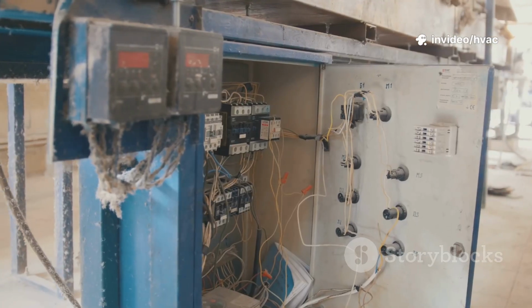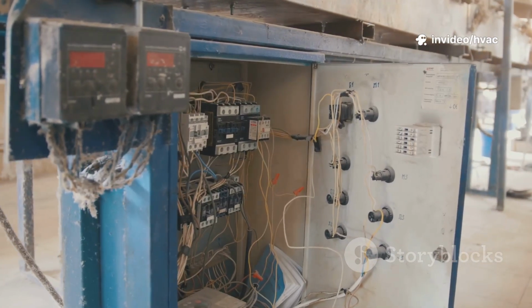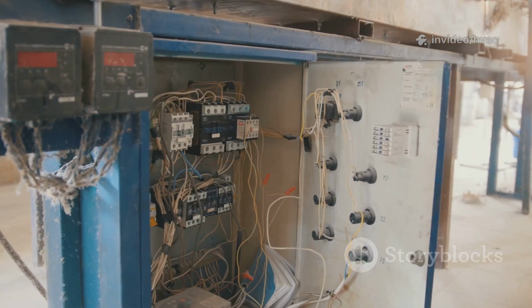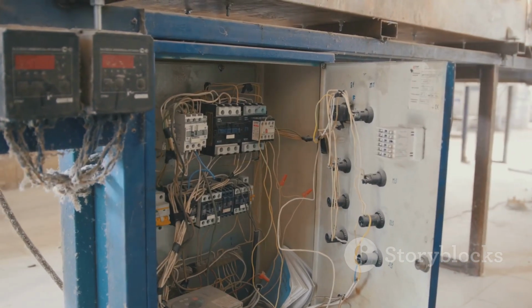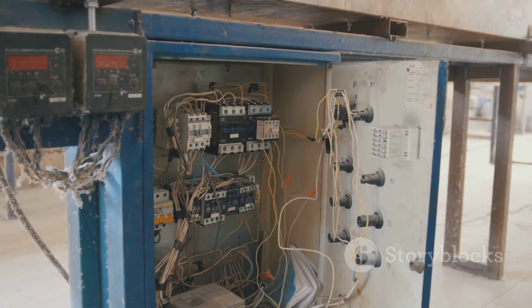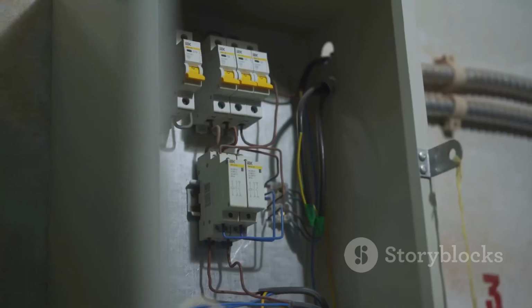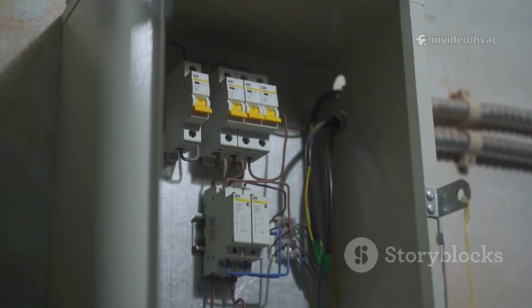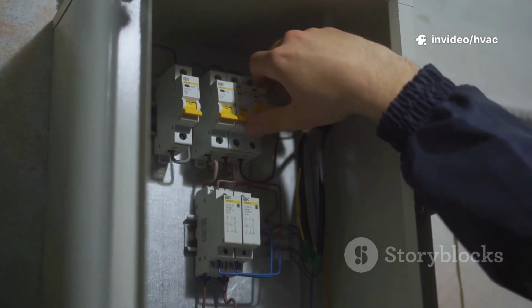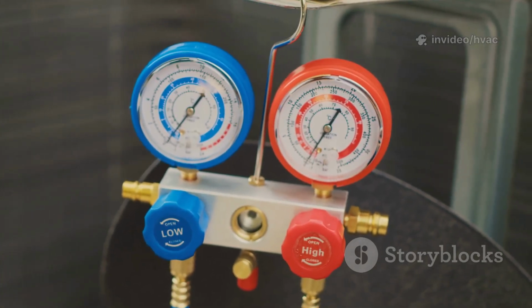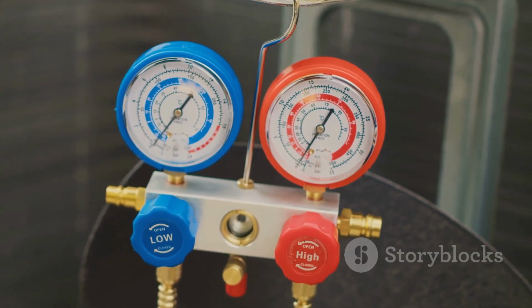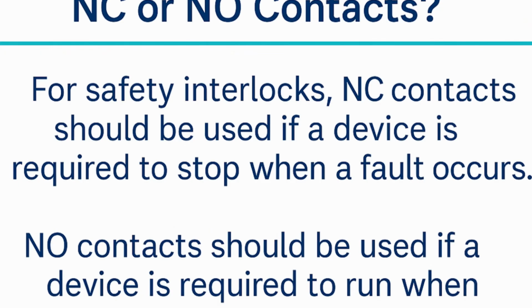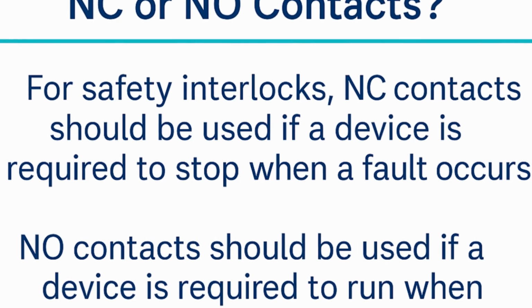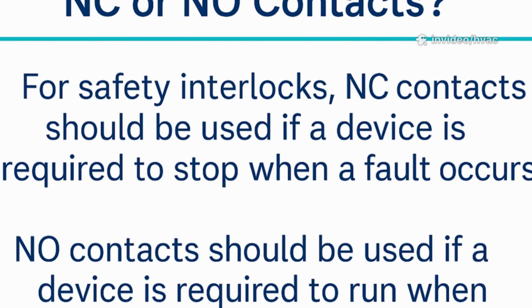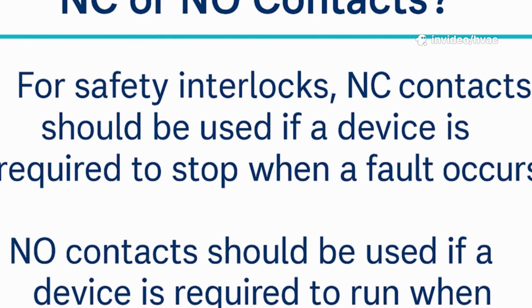For example, the chilled water pump starter has a NO auxiliary contact. This proves the pump is running. When the pump starts, the NO contact closes, sending a signal that the pump is actually on. NC contacts are closed at rest. Electricity flows until the device trips. The flow switch in the same system is NC. It stays closed as long as water is flowing. If flow stops, the switch opens and breaks the circuit. The low temperature cutout is also NC. If water gets too cold, it opens, stopping the chiller to prevent freezing.